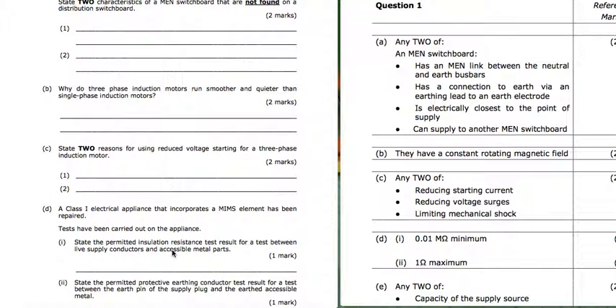C. Two reasons for using reduced voltage for starting three-phase motors. So reduced voltage will give us reduced starting current, it will give us reduced voltage surges, and it will limit the mechanical shock.